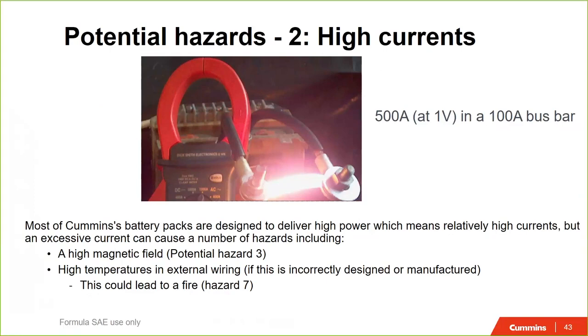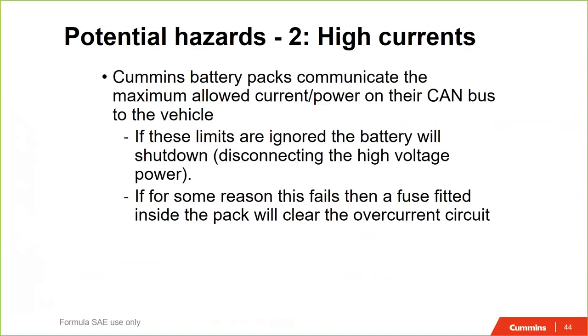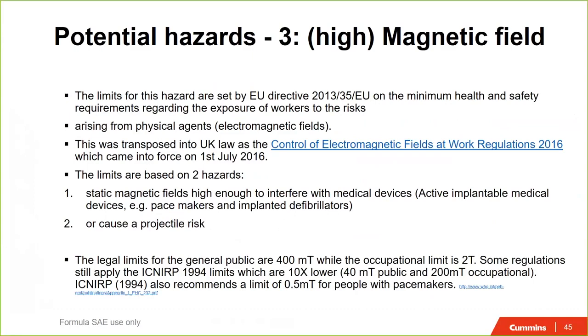The high magnetic field is a result of pulling a high current. Again, when we design, and those of you that are working on BMS design, make sure that you have safety interlocks before you can deliver that high current. If those limits are failed, the next step generally is that the fuse fitted inside the pack will fail. The EU very kindly provides some directives for looking at electromagnetic fields, which is our next hazard.